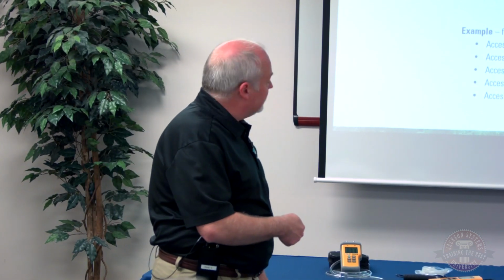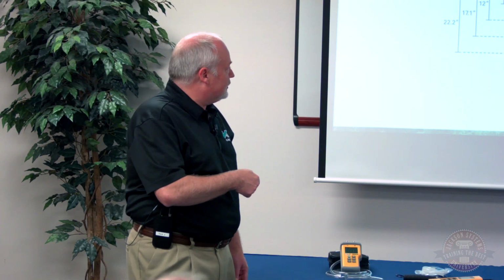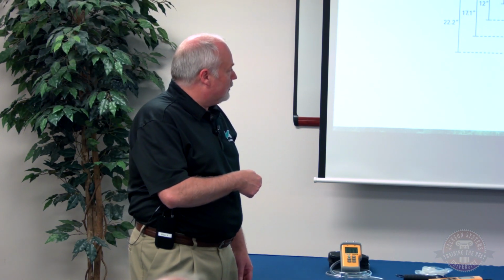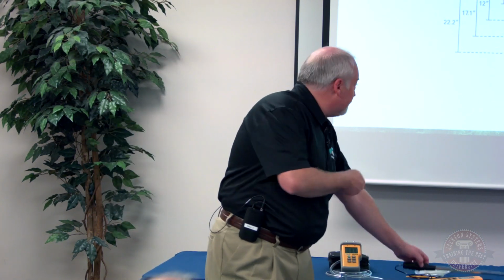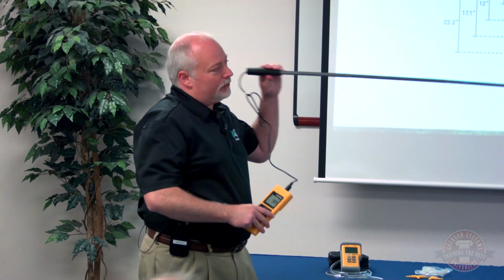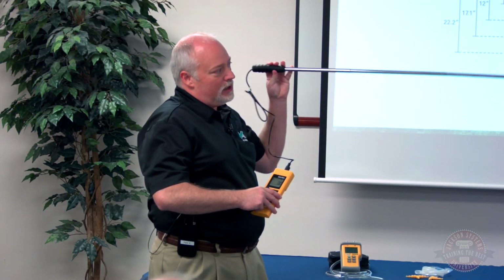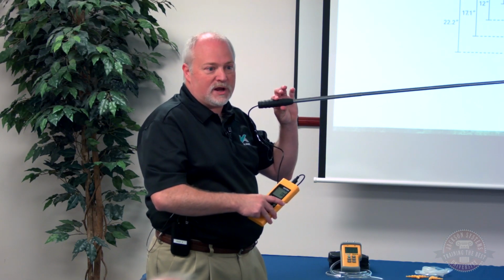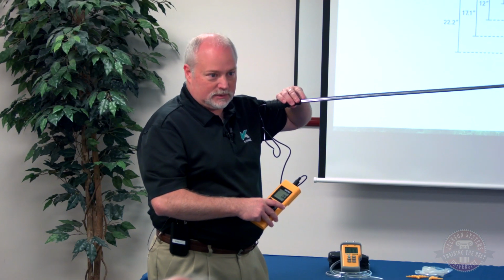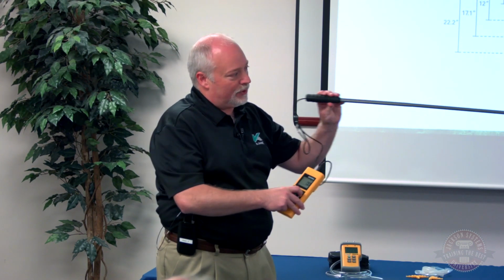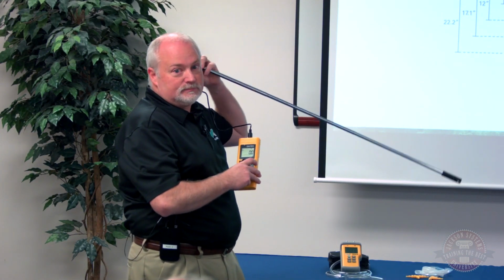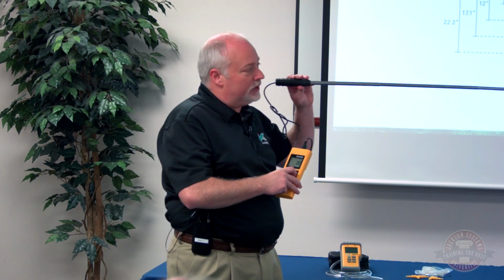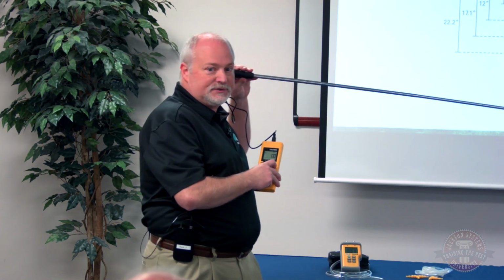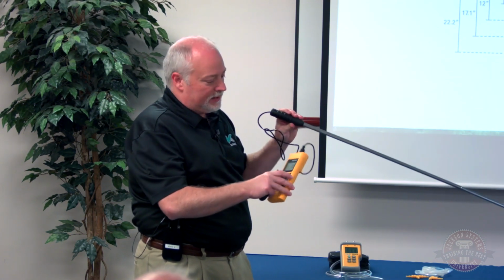So what that allows us, got a diagram here, is this gives us a good section to measure an airflow across that entire duct. When we put this in that first opening, we're going to hit the button to start, and we're going to want to slowly go across from one side of that duct to the other. We want to make sure that our vane is pointing the proper direction, with our airflow, not at a 90 degree, okay? So that we're getting good airflow, getting an accurate measurement. We're going to hit stop when we get to the other side. Pull it out, go into our next opening, hit start again, slowly go across that duct, hit stop, go into our next opening, okay, until we're done. Then that's going to average that reading that we've taken and give us a time average of what that entire duct is flowing. Okay?